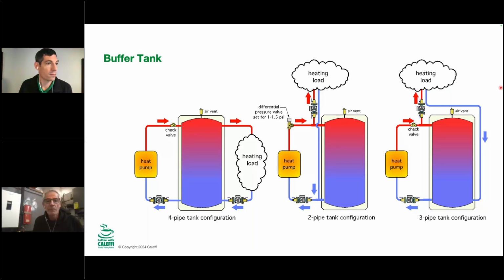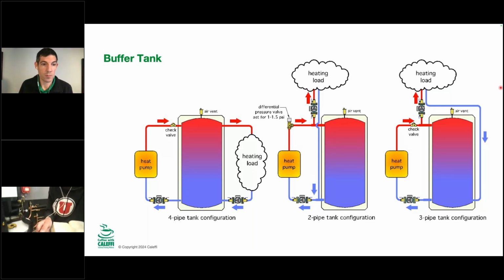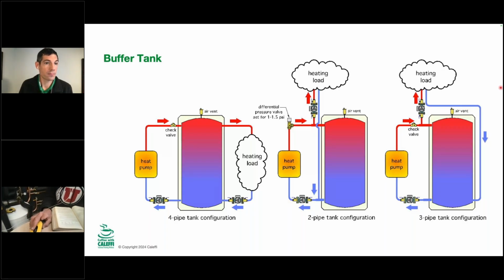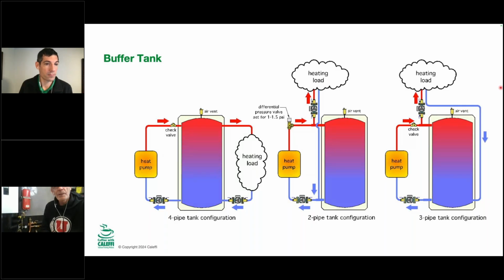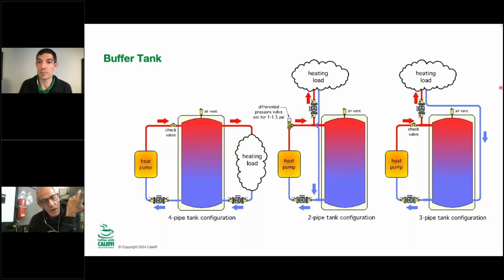I don't know if you can see it, I'll turn on my camera here, but I just put a heat pump, a Viessmann heat pump, in my shop with a buffer tank, and you can see the two pipes come off the side there. So my heat pump module right there ties into the buffer tank, and my boiler ties into the buffer tank too, and then my loads come off of the buffer tank. So any one of them, or they could be working together. The heat pump could, if it's not keeping up, kick on the boiler, they could work together, they could work independently, or I can be pulling hot or chilled water off that buffer tank without either of the inputs, which I'll call the boiler and the heat pump, running. So this one is pretty nice.